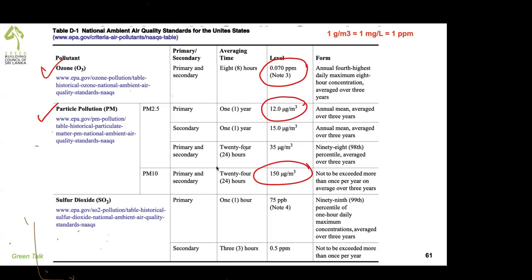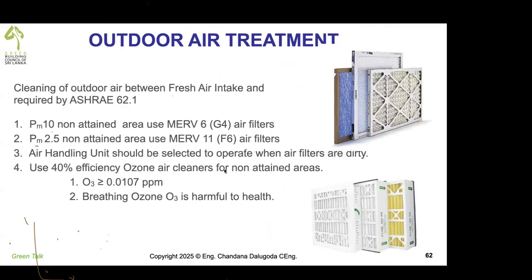Sulfur dioxide, 75 ppb. Now, for instance, particulate matter, if exceeds 12 and 150, they are PM 2.5, PM 10 respectively, you'll have to use air filters, special air filters. So you can see PM 10 non-attained areas, we'll have to use MERV 6 filter. G4 is European standard, MERV 6 is American standard. PM 2.5, you'll have to use MERV 11 filters.